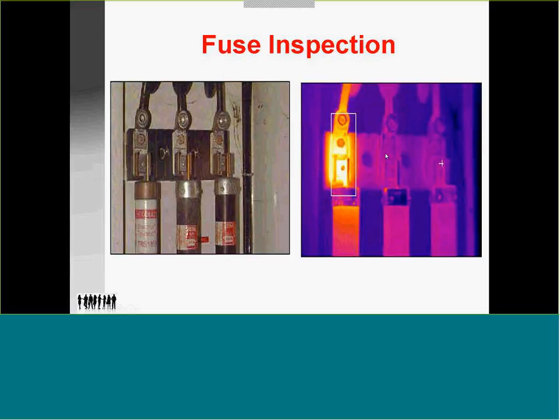Now, these are the same units when we look at it. Here, there's no erosion or what we call oxidation on the screws or on the surface, but look at the discoloration here. Now, in infrared photography or thermography, it more clearly shows the higher temperature, reaching about 250 degrees centigrade. What's showing us is there's a bad clip. Heat is being transferred into the connection.